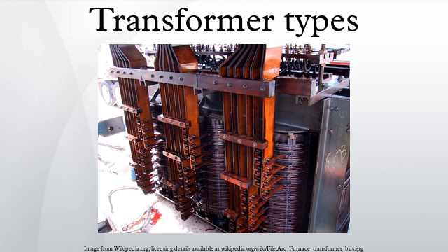Polyphase transformer. For polyphase systems, multiple single-phase transformers can be used, or all phases can be connected to a single polyphase transformer. For a three-phase transformer, the three primary windings are connected together and the three secondary windings are connected together. Examples of connections are Y-delta, delta-Y, delta-delta and Y-Y. A vector group indicates the configuration of the windings and the phase angle difference between them.